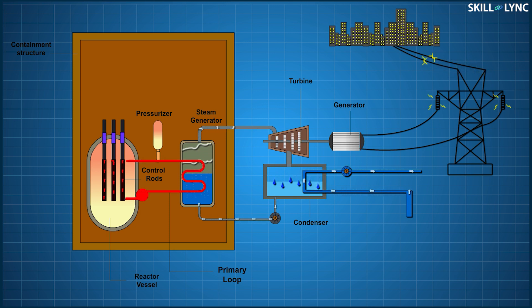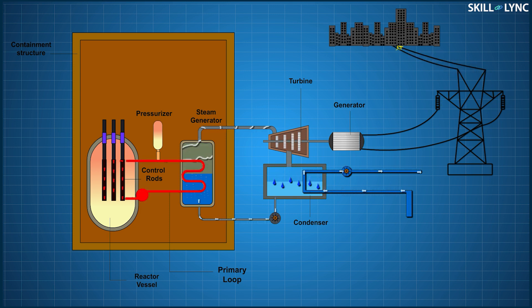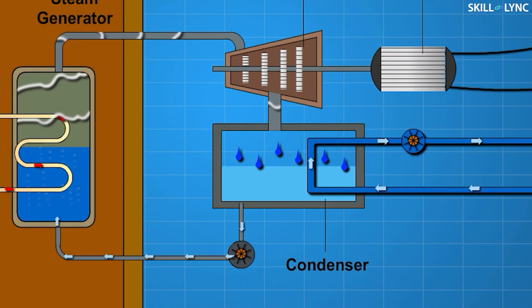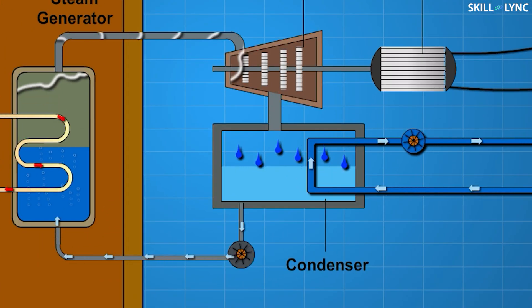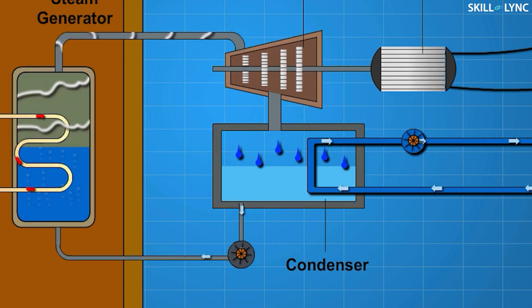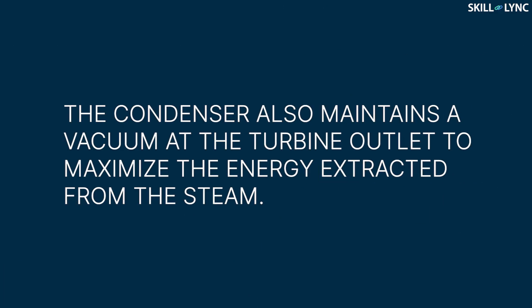The steam is then sent to drive a turbine, which in turn drives the generator. The secondary coolant or the steam is sent through a condenser to cool it down, and the water obtained is sent back to the steam generator. Apart from converting the steam into water, the condenser also helps in maintaining a vacuum at the outlet of the turbine. This causes a pressure drop in the turbine and hence the energy extracted from steam is maximized.